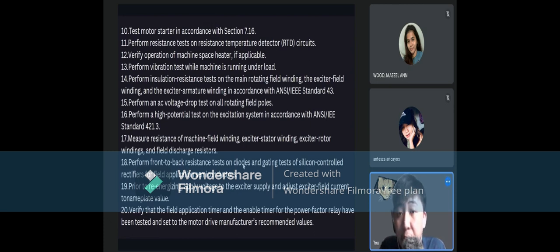in accordance with ANSI standard 43, which means measuring insulation resistance of armature and field windings of rotating machines rated from 1 horsepower or 750 watts or greater. 15. Perform an AC voltage drop test on all rotating field poles. 16. Perform a high potential test on excitation systems in accordance with ANSI Standard 421.3.